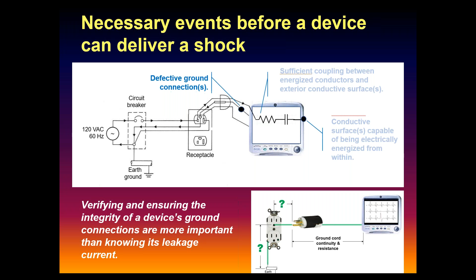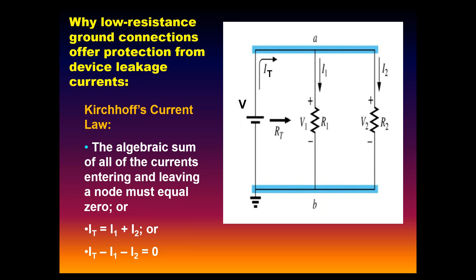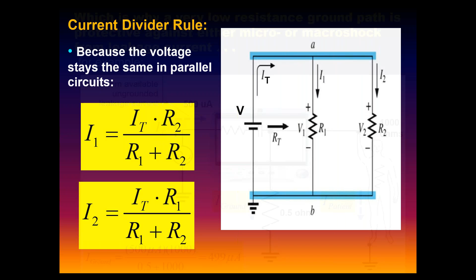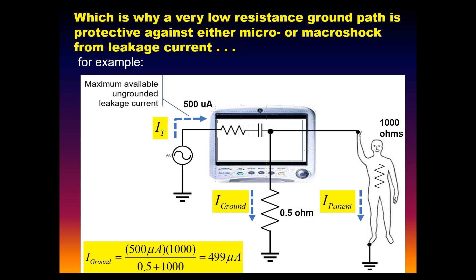And the reason it drains away is one of the fundamental laws, Kirchhoff's current law: the currents leaving a node have to equal the currents entering the node. This is where we get our protection from the ground. If I have a low resistance ground, say half an ohm, versus 1,000 ohms for a full person, and there's 500 microamperes of leakage current, that current takes the path of least resistance — most of it, 499 microamperes, goes to the low resistance wire ground. The patient only gets 1 microamp. This is why the ground on those devices is so crucial, because of Kirchhoff's current law and the protective effect of having that very low resistance ground.